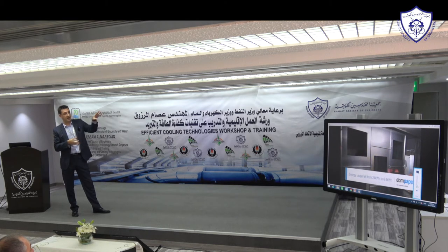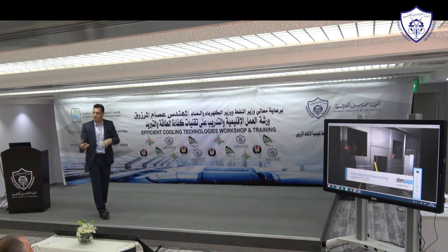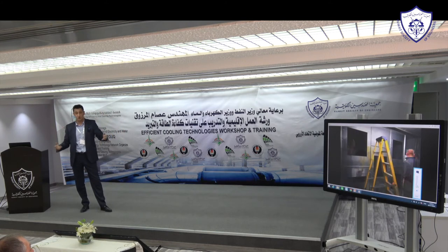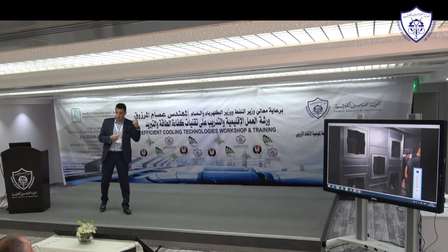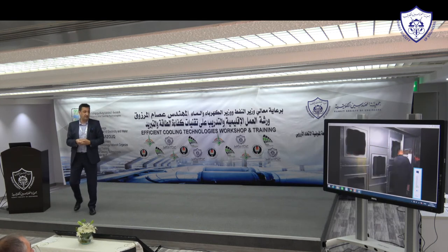They used a fan array of five centrifugal fans to achieve the same duty. This means rather than one fan, there's built-in redundancy — even if one fan fails, you can still maintain duty in an emergency condition and the plant will still run. The key result: five fans replacing one reduced power by 73%, with a payback of just 19 months.